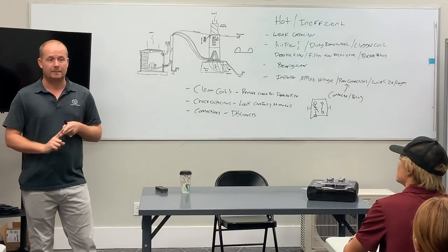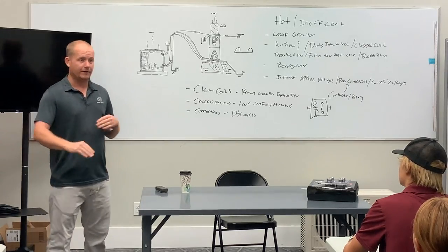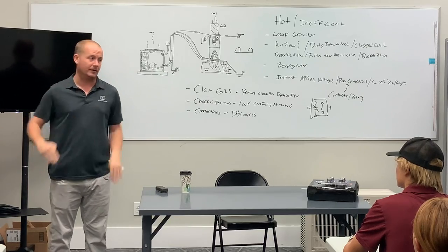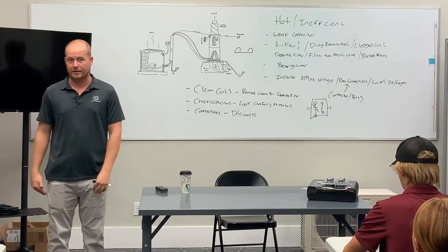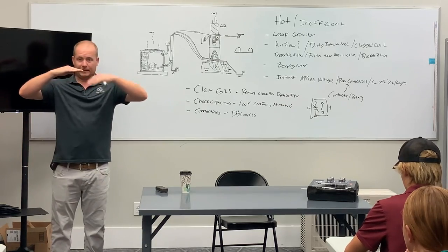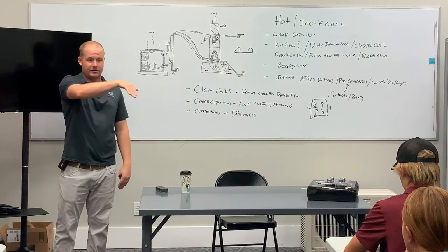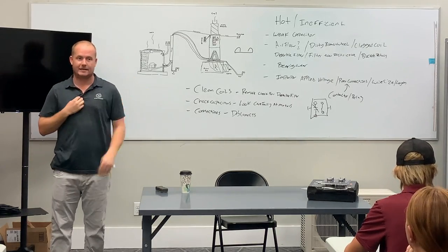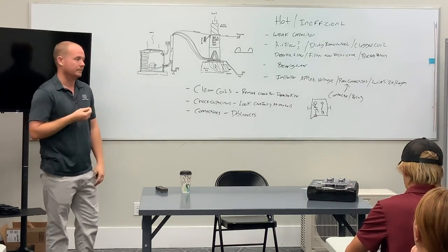Drains improperly pitched at the air handler. If a drain is perfectly level and there is a way to get it pitched properly, that's something that should be redone. A lot of times you'll see that it's perfectly level right here, but then when it goes back and returns, there's plenty of space. They could have pitched it more, and that's going to result in a better long-term result.